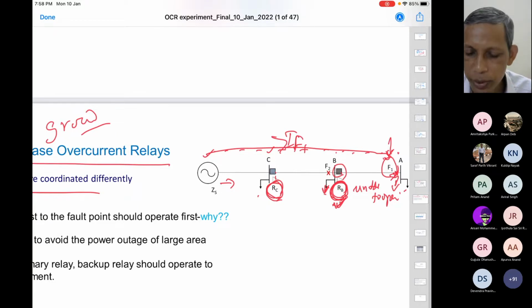Furthermore, RB is a relay. From relay to breaker, there is a command and there is a communication. The communication wire is being damaged by a rat. The battery is not functional. The trip coil has some problem, and so on. So any device, any arrangement has certain problems. So then what will happen? If you have a problem in opening the breaker, due to whatever reason, or the relay itself has a problem, or the relay characteristic is such that it is not able to detect that fault, or your setting is improper, or I put it into maintenance and after the maintenance I restore it, I fit it in the cabinet, but somehow it is not operational. Then in that case, this one acts as a backup.